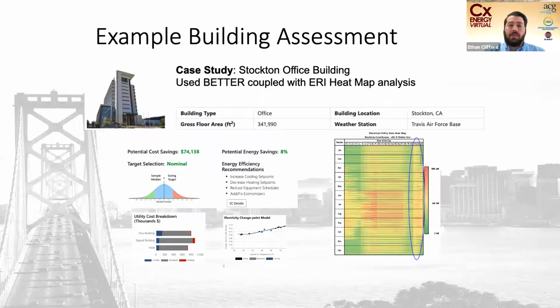So that was one anomaly. With that, we ran our IDEA tool, an interval data energy analysis tool, which generates this heat map. This heat map gives us better insight into how the Better tool was functioning. We noticed there's a time around 21 hours, so around 9 p.m. at night, and we wondered what's causing this pretty large increase, because the darker red means more demand, and the lower green means lower demand on the electricity bill.